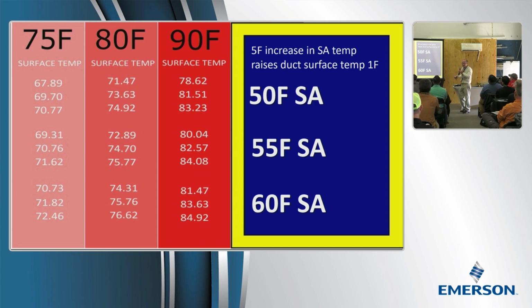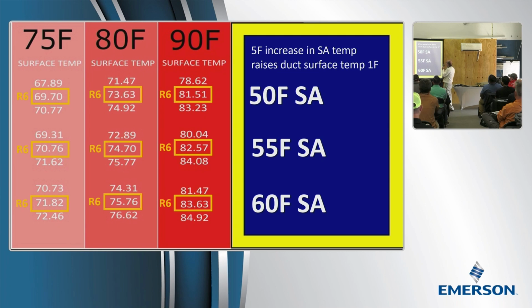Most of these problems have to be solved before the duct is installed. Here's what happens. A 5 degree, we'll look at R6, a 5 degree increase in the supply air duct. We were running air leaving the coil at 50 degrees, but the cabinet's sweating. So I'm going to speed up the air handler, and when I do, the air leaving is now 55. We raised it 5 degrees. You get about a 1 degree increase in your duct temperature from a 5 degree rise. So that's your second question answered.